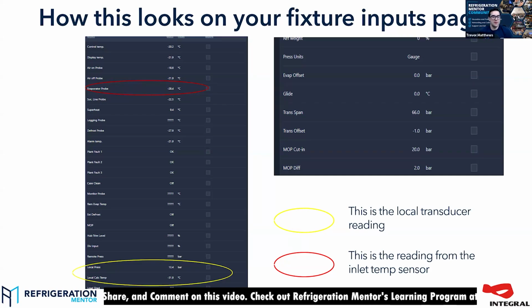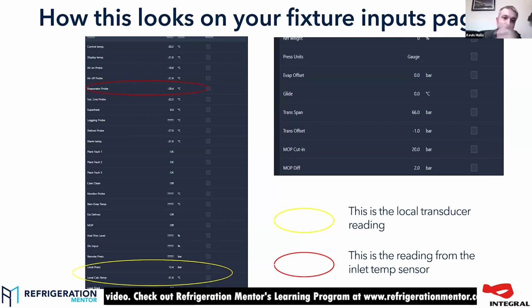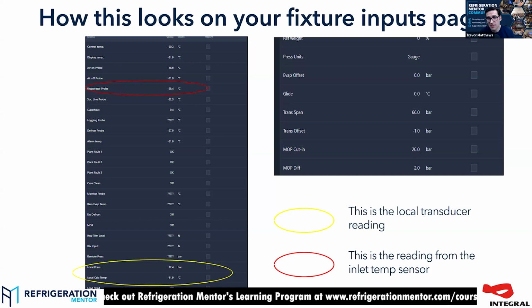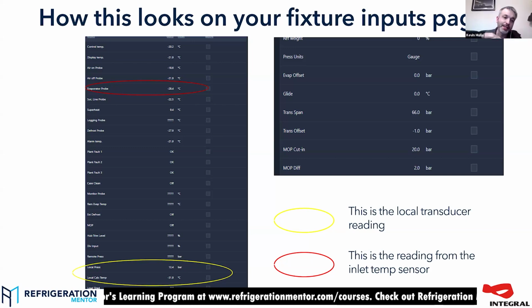And so, Kevin, just to be clear, this is using 2 temperature probes, not the pressure and temperature at the outlet of the coil. Yes. So you just explain that for everyone, because a lot of people only know that it's the pressure and the temperature controlling superheat. So there's different ways to do that. Yeah, absolutely. So the correct way to do it, the way we've started doing it more again now, is to use a transducer to give you your suction pressure, to give you your evaporating condition, and to use a suction probe, an outlet probe on the coil. So with those 2 numbers, you can work out your true superheat.